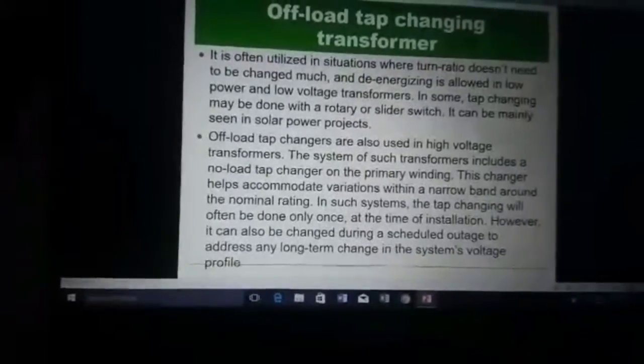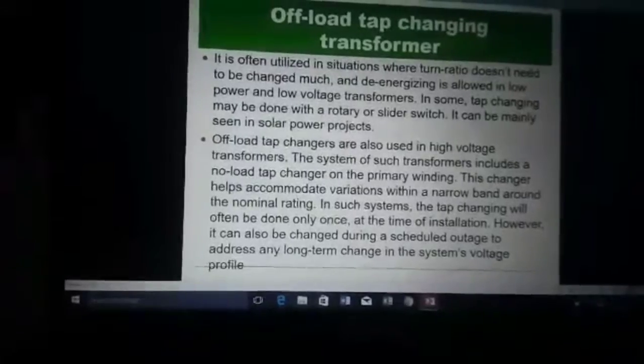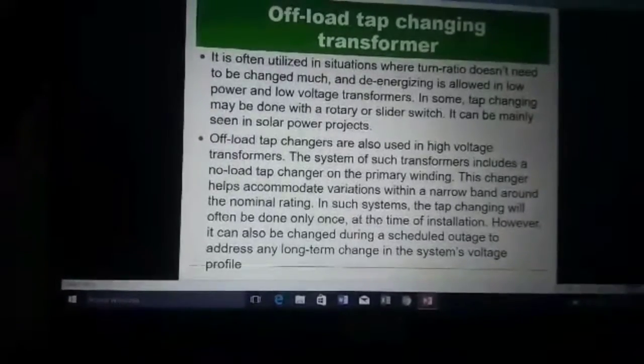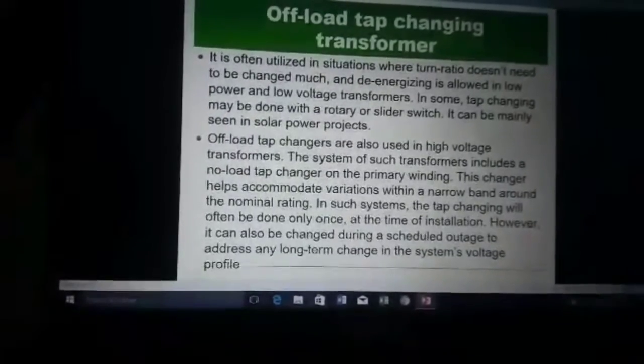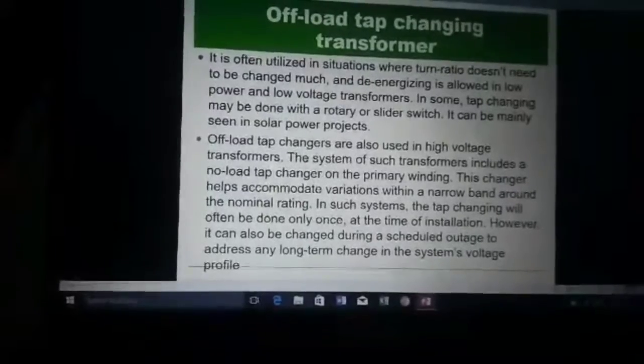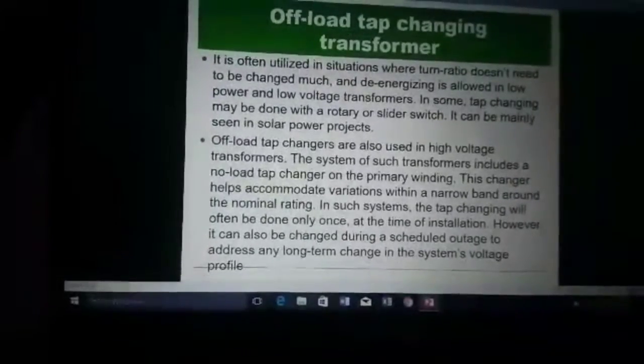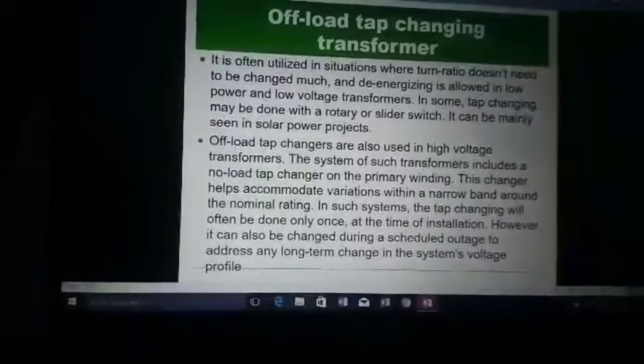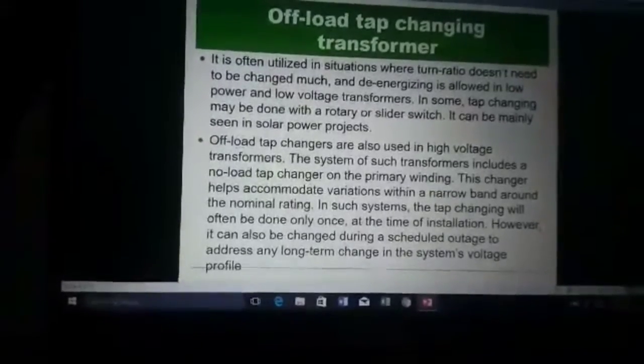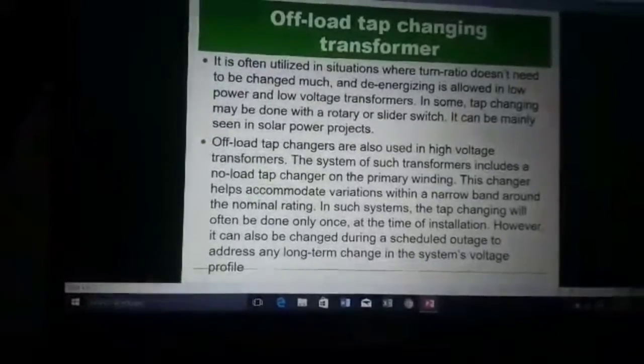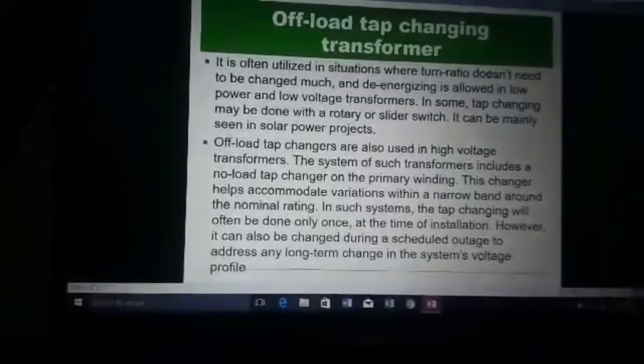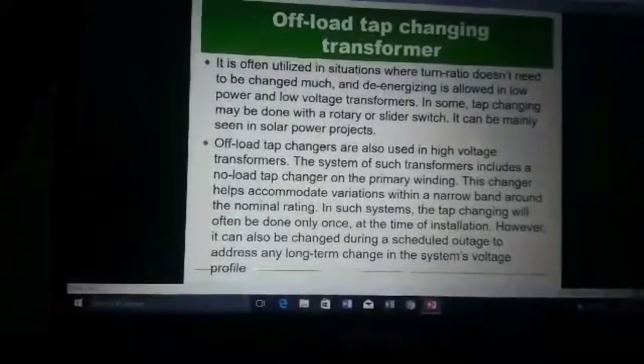Next, it is often utilized in situations where the turn ratio doesn't need to be changed much and de-energizing is allowed in low power and low voltage transformers. In some, tap changing may be done with a rotary or slider switch. It can be mainly seen in solar power projects. Offload tap changers are also used in high voltage transformers.